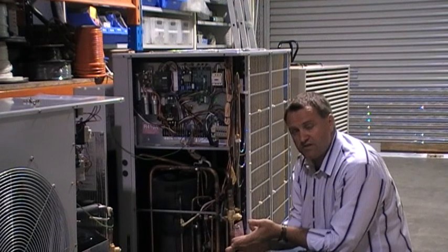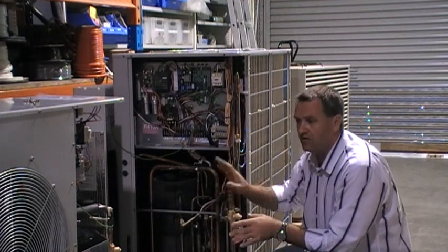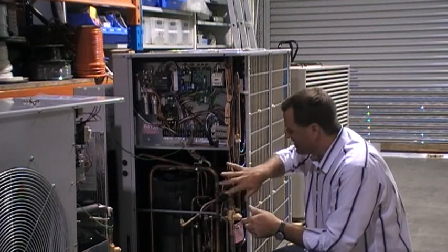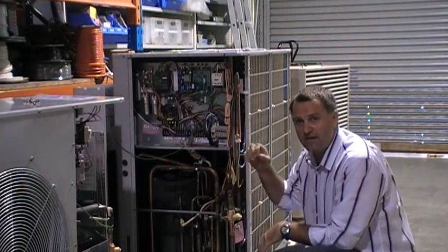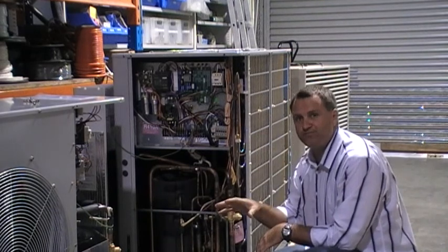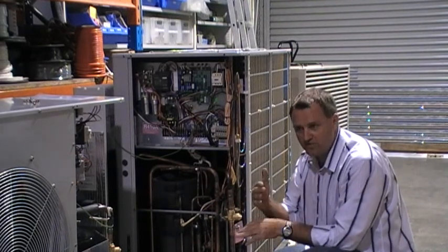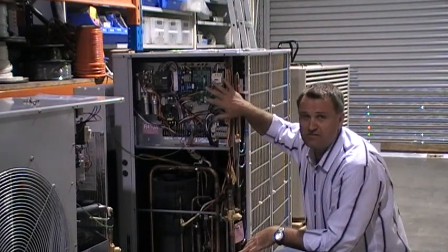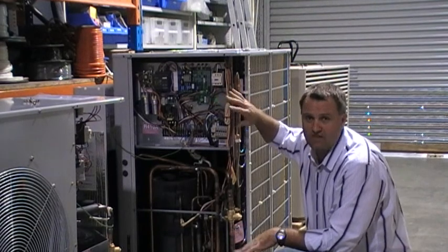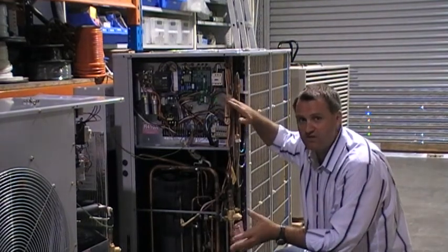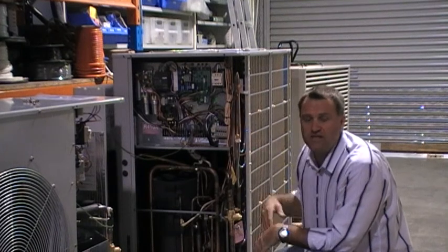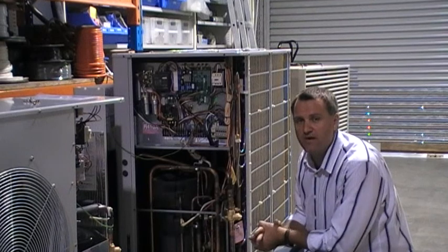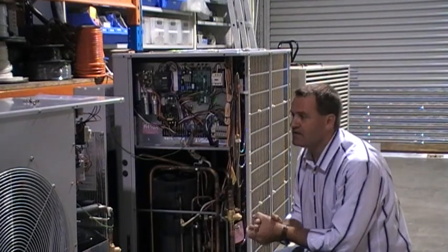The disadvantages with digital scroll and with standard cycling is that compressors, when they start, start fully loaded. They run at 100% straight off the bat, whereas an inverter will slowly speed up. But these guys put soft starters and things in their units to make sure that your lights don't dim as much as they could. Generally speaking, in suburbia that won't matter, all the power supplies are good, but sometimes in rural situations where the power supply is not so great, you can get lights and things like that dimming.